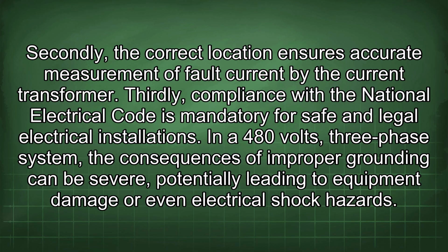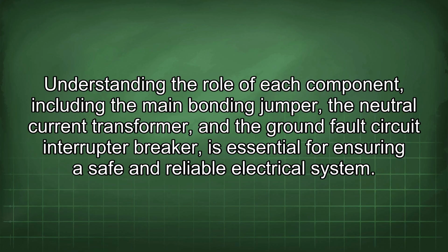In a 480 volts, three-phase system, the consequences of improper grounding can be severe, potentially leading to equipment damage or even electrical shock hazards. Understanding the role of each component, including the main bonding jumper, the neutral current transformer, and the ground fault circuit interrupter breaker, is essential for ensuring a safe and reliable electrical system.